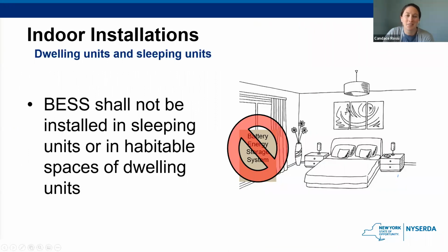But continuing on here, for indoor installations, which both dedicated and non-dedicated must meet, is that they shall not be installed inside a dwelling location. When energy storage fails, it may release toxic fumes that can overcome a human being very quickly. So for these reasons alone, the risk is too great. I don't know if you really want to be sleeping next to your storage system, to each their own, but the code has decided that they cannot be installed in dwelling units or sleeping units.